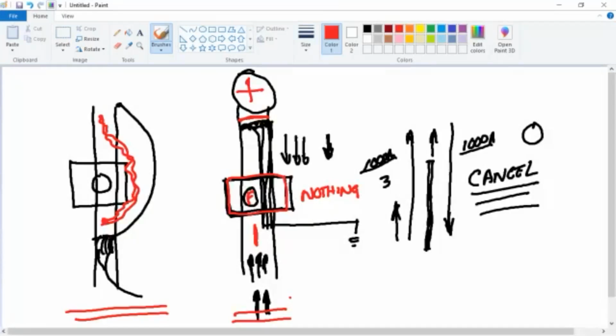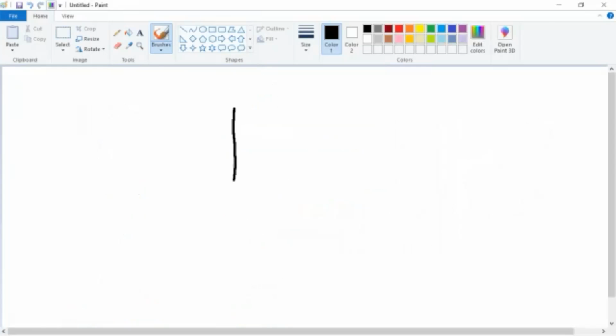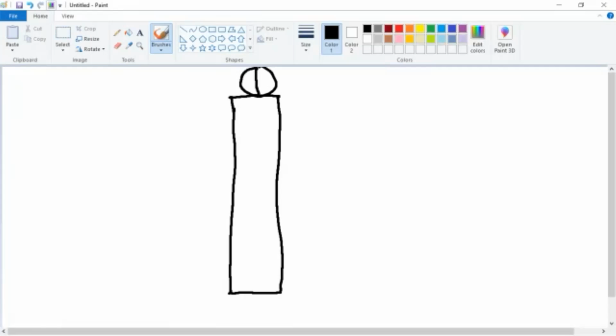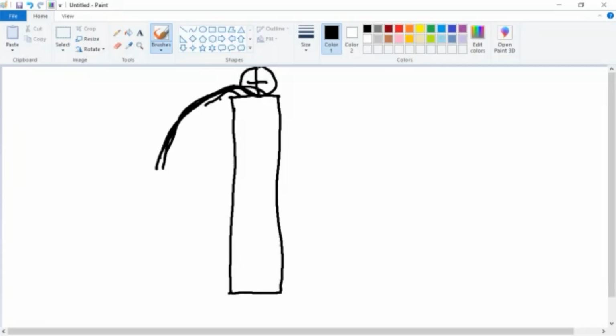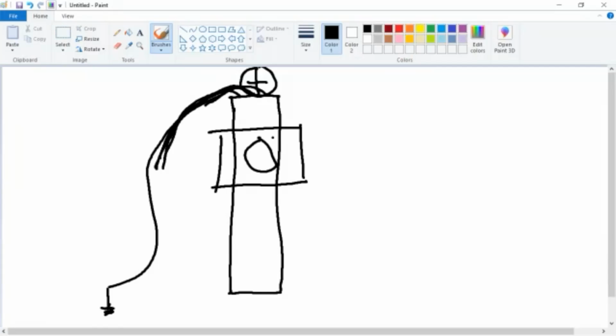The problem will occur when you do this. We use a piece of primary cable, and I've seen the guys do this before. They take the ground all the way to the top. This is my elbow connection right in here. Then they come out with grounds, and this is what they'll do. I kind of drew that wrong. Let me undo that. They'll come out with their grounds like this, and they'll twist them all together. And then they'll go down to the ground rod with it. They'll slap the indicator on right here. What's the problem?